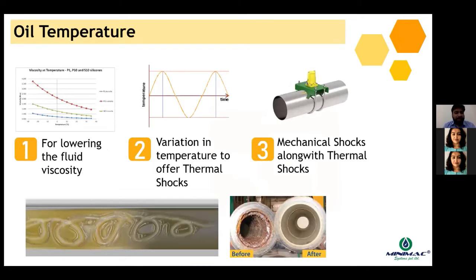The third one is oil temperature. The first point under oil temperature is that we all know that when you lower the fluid temperature, the viscosity goes up. And when you increase the fluid temperature, the viscosity goes down. So the preferred temperature is always on a higher range. And that's why we call flushing activity hot oil flushing activity. Because when you heat up the oil, you're actually reducing the viscosity of the fluid, and thereby you are having better turbulent flow in your pipings.